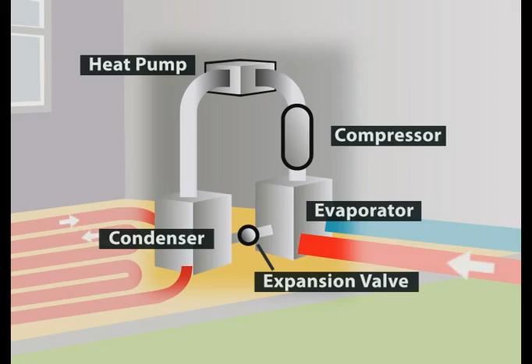Mike, let's talk about the ground loop. When would you go for a borehole, say, and when would you go for a horizontal trench? Well, essentially it depends on how much of a footprint you have for your property. If you've got a massive school playing field and you're absolutely sure that you don't want to sell that on at a later date, then you can go for a horizontal system, which is slightly cheaper, not quite as efficient as a borehole system, but there are cost savings there. However, if you've got a much larger building load and you don't want to sterilise that ground, generally boreholes are the favoured method, and those can vary from anywhere between 50 to 200 metres deep.